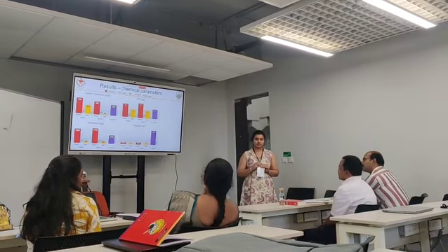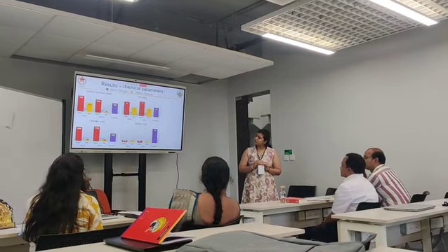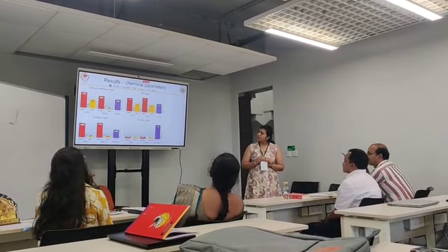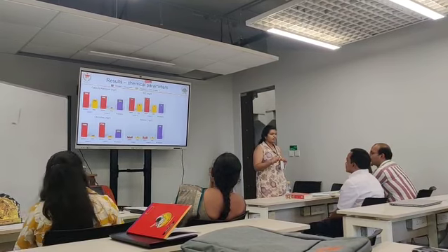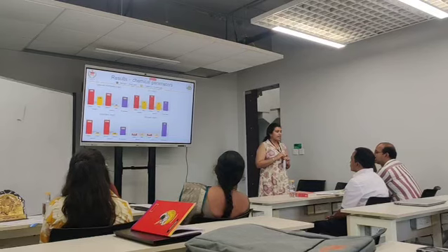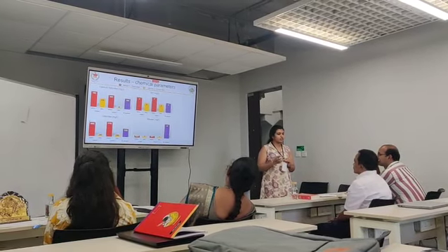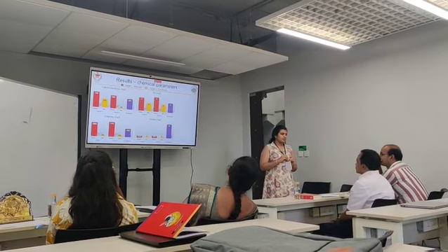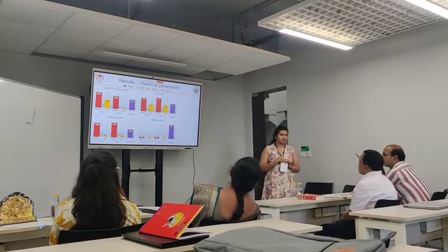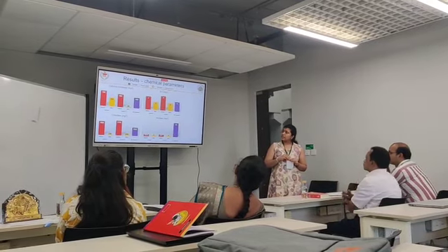So you check this calcium hardness: before it shows 600, and almost a 10 times drop after. We tried and erred with the filter layers, and due to the continuous changes in the filter media, we got those results. The same is not true for sample 1, 700 to 416.